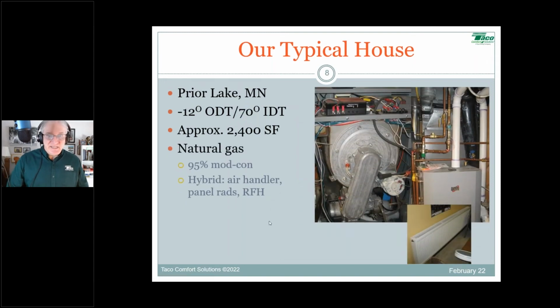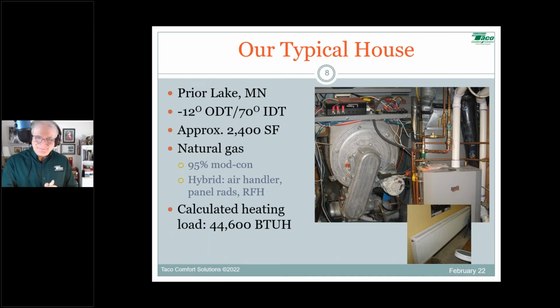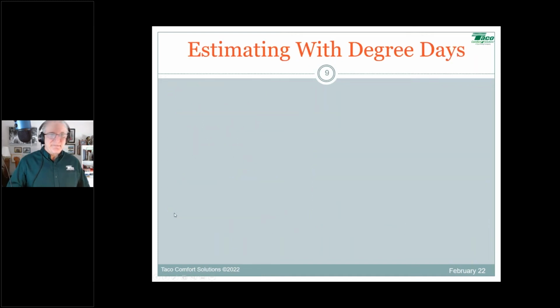Well, here we go. It's heated with a 95% ModCon boiler, as you're looking at there. It was an NTI, and it's a hybrid system. We have an air handler for upstairs, panel radiators and radiant floor heating in the lower level. All right. And here it is, the calculated heating load, 44,600 BTUs. Interesting, huh? I was shocked when I did the math like 3 times and it came up with that 44,600 BTUs, and that's an accurate number. So it's interesting how when you really do the math, the BTU load actually can be surprisingly low. This is a 2,400 square foot house in Minnesota with a minus 12 outdoor temperature, 44,600 BTUs. So let's get into estimating fuel consumption using degree days.